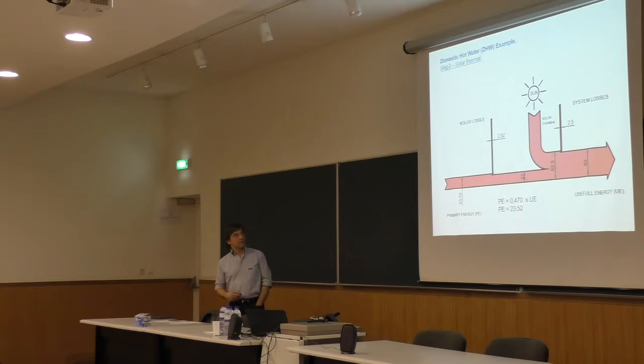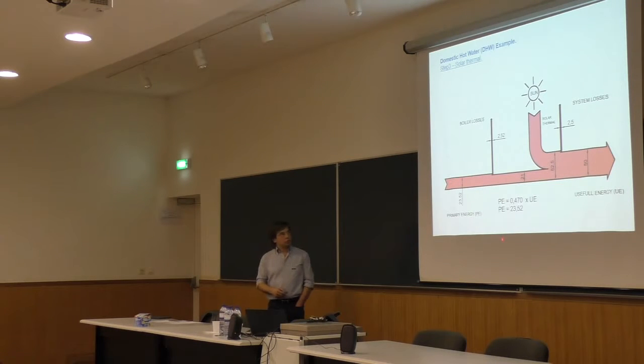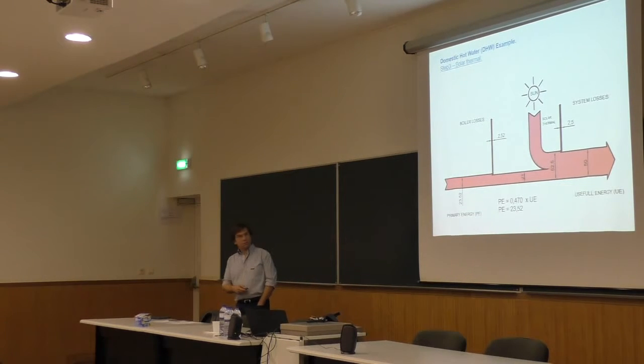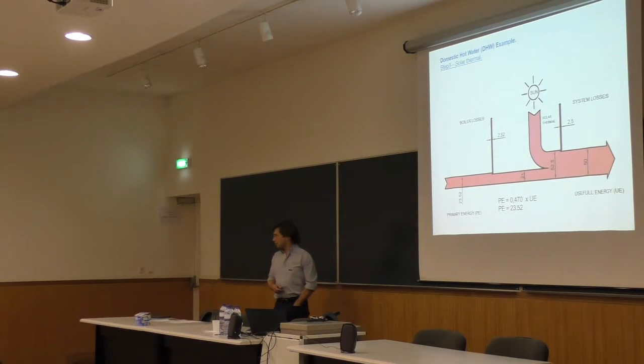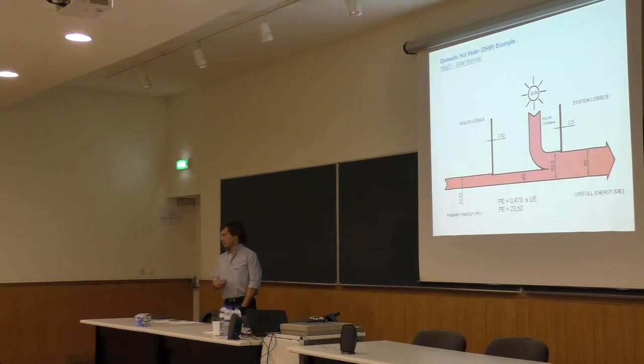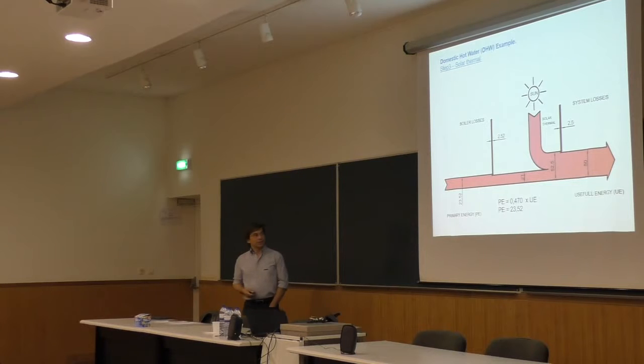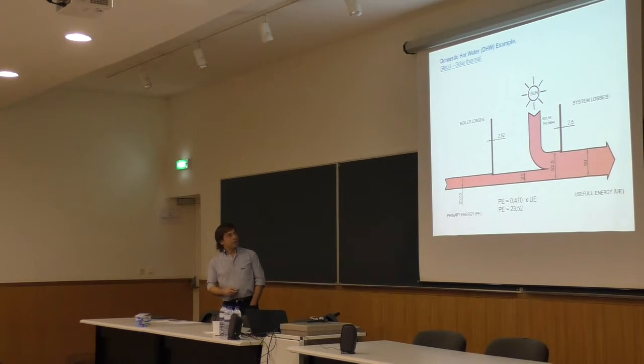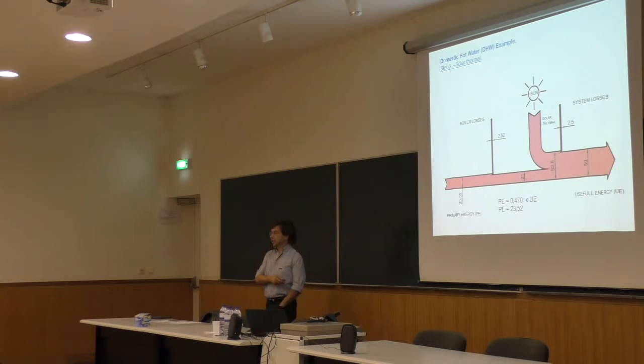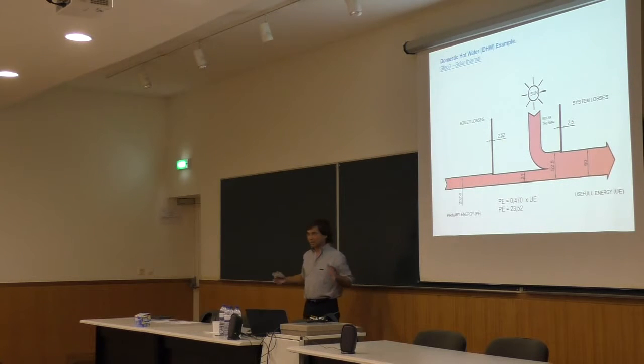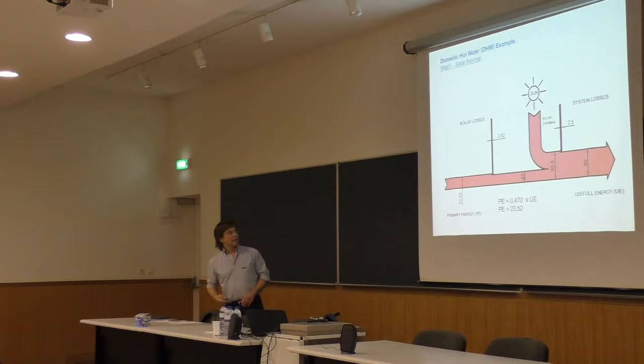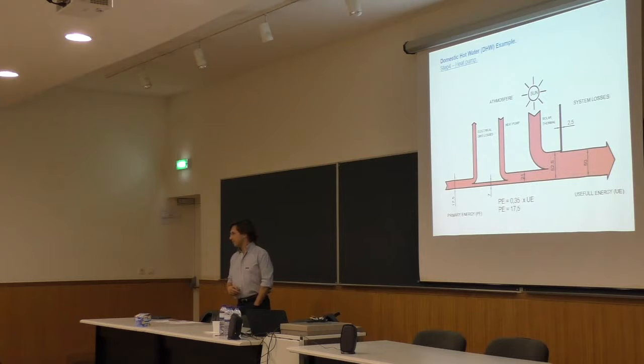And if we have a solar thermal system, we can expect on average, in Lisbon, Portugal, 70% of the needs supplied by the solar thermal system. And then we will only need 30% backup energy from the boilers. Okay? And now we are reduced to 23 units of primary energy, from 140. And at this stage we could already be nearly zero, depending on the definition of the country. What is nearly zero? How near to zero should you be? But you can do even better, because we have such a small amount of energy required on top of renewables. You can add a heat pump. A heat pump is also renewable energy.